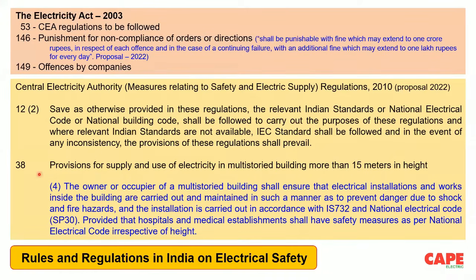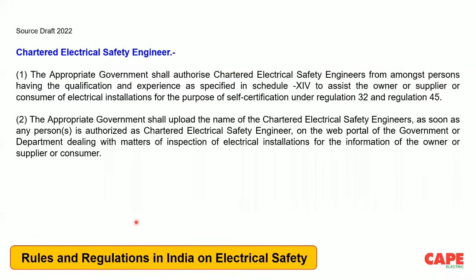For example, one of the regulations which talks about within the consumer premises is regulation number 36 earlier. Now in the new proposal, it's regulation number 38. It says the owner or occupier of a multi-storied building shall ensure that electrical installation and works inside a building are carried out and maintained in such a manner as to prevent danger due to shock and fire hazards, and the installation shall be carried out in accordance with IS 732 and the National Electrical Code. Provided that hospital and medical establishments shall have safety measures as per the National Electrical Code, irrespective of height. So probably this is new information. The new regulation says that you should carry out your design, erection, and installation as per IS 732, so compliance to IS 732 is becoming mandatory in some buildings, especially high-rise buildings of more than 15 meters height.